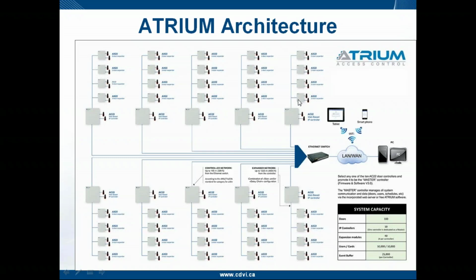When you've done that, the controller that's been set as an expander is now going to be a door expander. That expander will communicate through an RS-485 bus to the controller you're going to connect it to. It is not connected through an IP port on the network. So all the expanders are connected to the controller they're associated to. One controller can accommodate 4 door expanders, and that's on an RS-485 bus. Use network type cable, Cat5 or Cat6, to establish that communication. The overall distance of the loop on the expander bus is a maximum of 4,000 feet, 1,220 meters. So you can have a 4,000 foot cable run to accommodate the 4 door expanders.